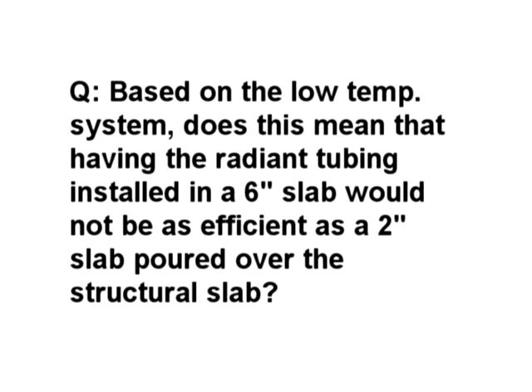Based on low temperature system, does this mean radiant heating tubing in a 6-inch slab would not be as efficient as a 2-inch slab? The answer is it's always the case that when you have a 6-inch slab, you have to pump a lot more energy into that slab. Thinner thermal masses are much preferable, because look at this in terms of temperature and recovery rate as well. What we used to think of as pickup in the system. This is why outdoor reset makes so much sense with these systems. You want to be energizing the system slowly, and being able to adjust it to outdoor temperature rather than trying to do big pickup exercises where you have to dump a lot of energy in. So I would say 6-inch slabs are not a very good choice in terms of response. The lower the temperature, the less response you're going to get.